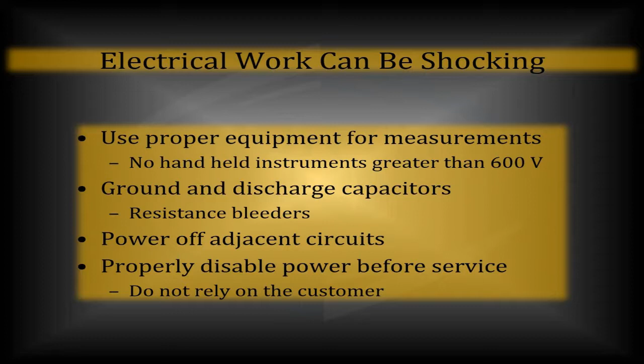When it comes to grounding, you want to make sure that grounding protection's installed. All electric systems and equipment got to have some kind of grounding protection to help prevent the unintentional energizing of any metal components within the system, including the boxes, the switches, the motors, the conduit, possibly even metal pipe that's adjacent to it, like copper. The grounding system should be at 0, allowing the current a safe path of least resistance in any case. That is what you want to do to ensure that if the system becomes energized, it's going to trip that breaker.